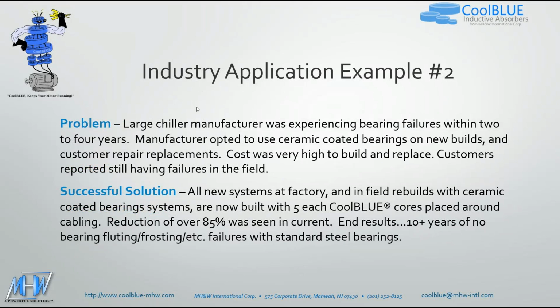This is a large chiller manufacturer. They were experiencing bearing failures within 2 to 4 years. The manufacturer opted to use ceramic coated bearings on new builds and customer repair replacements. The cost was high to build and replace. Customers reported still having failures in the field.